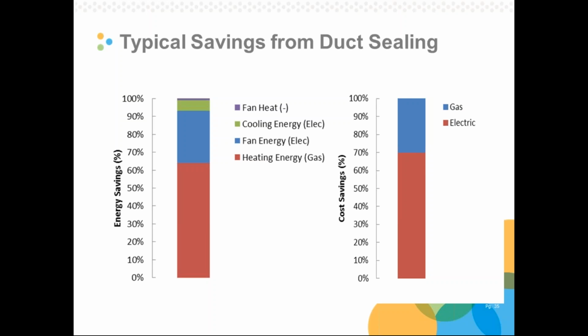The second biggest savings is from fan energy. We go from 7% to 1% duct leakage, and we save somewhere around 12 or 13% of our fan energy. We have a few more minor components of savings. There's cooling energy, which, since we're not a cooling dominated climate, we would naturally expect to be smaller. And then there's fan heat, which is a little bit complicated to deal with, and we essentially ignore it because it's usually less than 1 or 2%. So energy savings are predominantly gas, and then there are also significant electric savings.